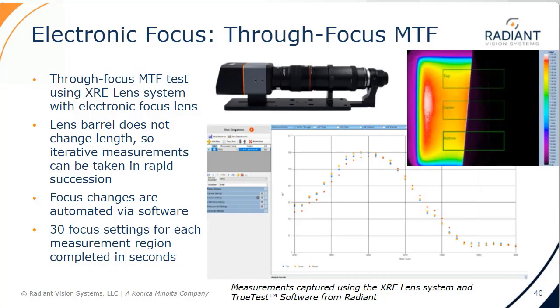In this example, the XRE lens system has run over 30 focus settings at each measurement region to find the best focus result at around, what we're saying is, 3560 motor counts. And in the commercial system that we are releasing today, the motor counts are all calibrated to actual physical distances.